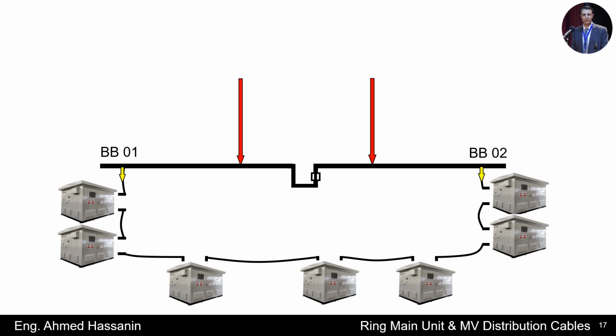We see two medium voltage incoming feeders in red colors, which feed two medium voltage switch gears named busbar 1 and busbar 2. The two medium voltage switch gear, busbar 1 and busbar 2, feed all kiosk transformers in the ring distribution system. So we must know that the ring distribution system is a group of kiosk transformers connected to each other by medium voltage cables.